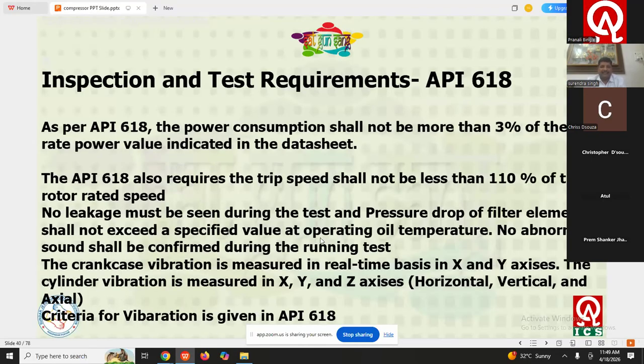There are criteria given in the API that the power consumption shall not be more than 3% of the rated power value indicated in the data sheet. It means if I am declaring that my compressor consumes 100 kilowatt, then it cannot go beyond 103, because 3% is the tolerance given. So my compressor shall consume a maximum of only 103 kilowatt. This is one requirement and the tolerance given in 618.